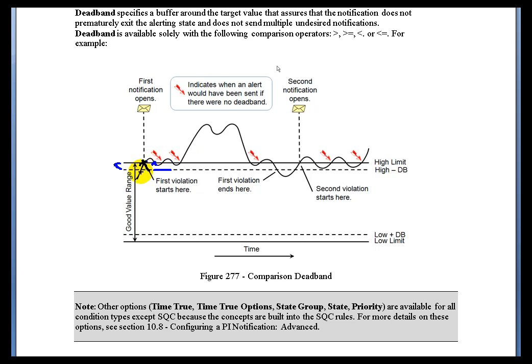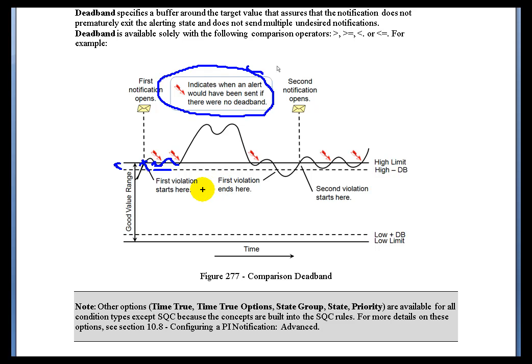As you can see, this is one of those situations where it keeps wobbling in and out of the Alarm State. Now, at each point where it goes into another Alarm State, you would expect to get another notification sent, but at this point we're not doing that. This indicates that we would have sent an Alarm if we hadn't implemented a Deadband. So we do strongly recommend that you use Deadbands — they're a great way to avoid Nuisance Alarms.